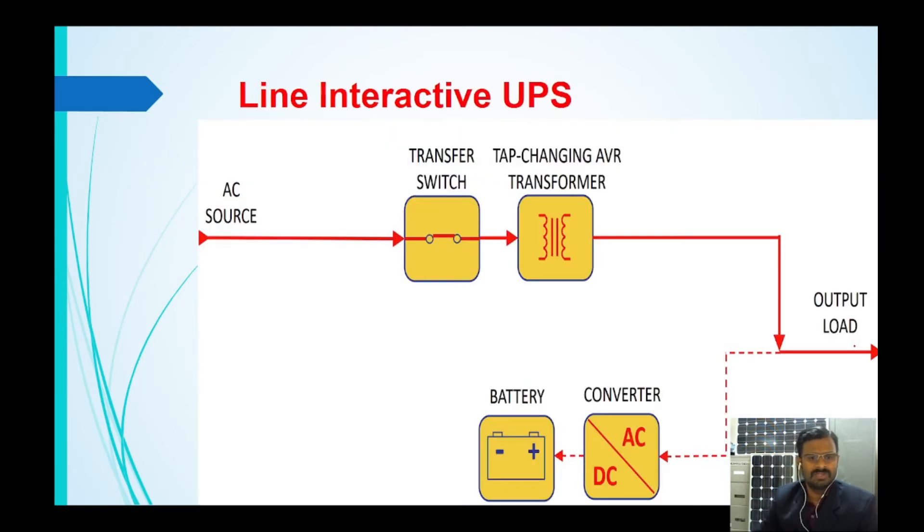How does this line interactive UPS function? When the utility power is there and the transfer switch is closed, the power is being transferred to the load through the transformer. Also a certain amount of power is given to the AC to DC converter and it goes to the battery to charge the battery.